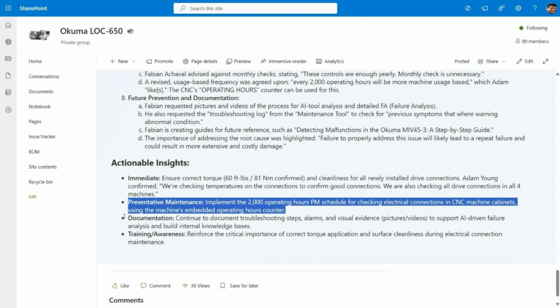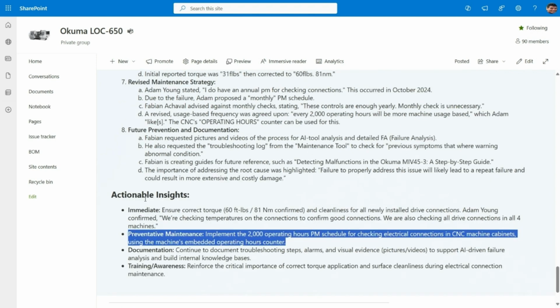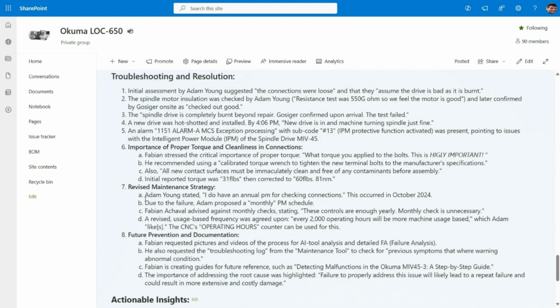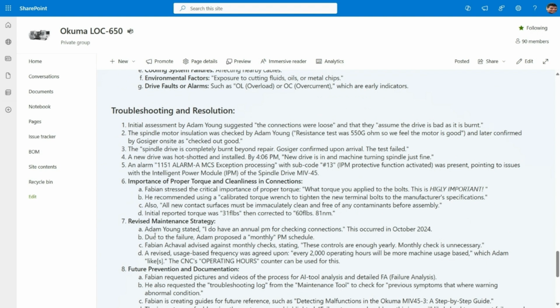Precisely. And just to really hammer it home, the most important takeaway for preventing this specific type of failure, the loose connection leading to thermal runaway, is that annual thermal imaging, at minimum, is probably the single best early warning system you can implement. It's non-invasive and highly effective at spotting these developing high-resistance issues before they cause chaos. That's a really powerful point: catch the heat symptom early, without potentially introducing a new problem by messing with a good connection. Exactly. You verify stability without inducing instability.